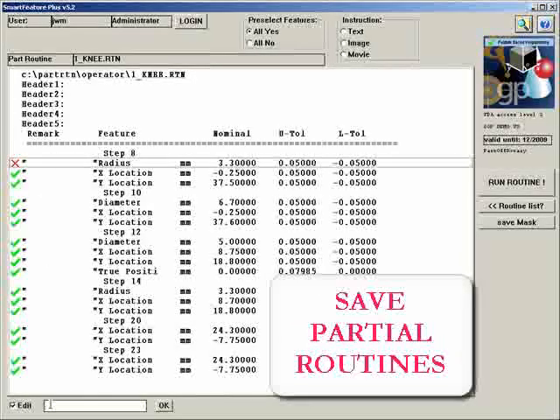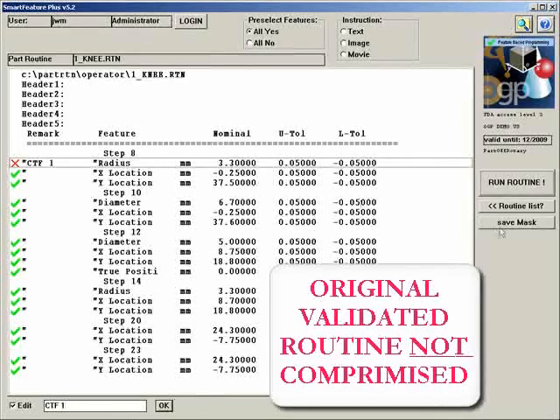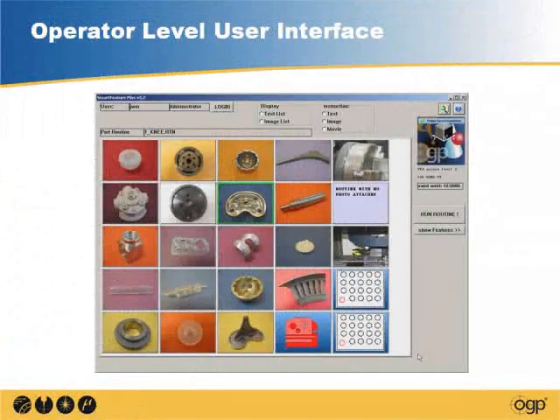This is showing that, relative to compliance, typically you have to validate a program. So you might have a first article program that measures everything, and then occasionally you might pick just sub-features of that, just critical features. You can pick the features that you want to measure, and then it figures out what kind of datums to use in order to measure those critical features. And then the original validated routine isn't compromised because you're still using that same program. So it's a slick way of validating one program but using subsets of the program to get through it without revalidating.